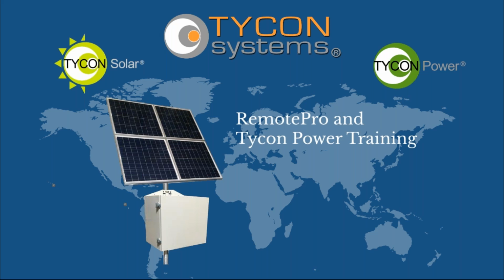Now, let's say that you had the 4 panel system like you see pictured here, that's 340 watts. And let's say your site or your project doubles, you can absolutely just buy another solar panel array like this with the mount on the same pole. I would give it some distance on the height so you're avoiding any shading, but you can absolutely tie it directly into that battery bank, as well as add more battery banks to that with the enclosure.